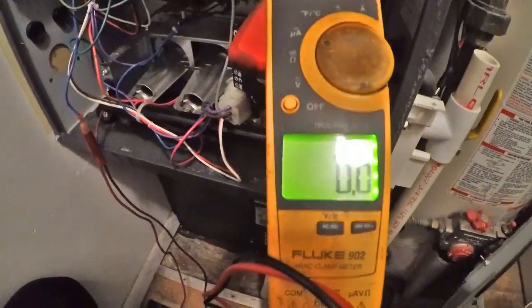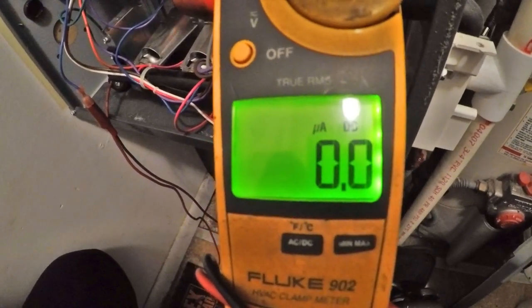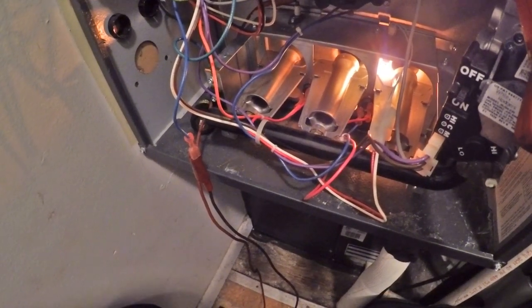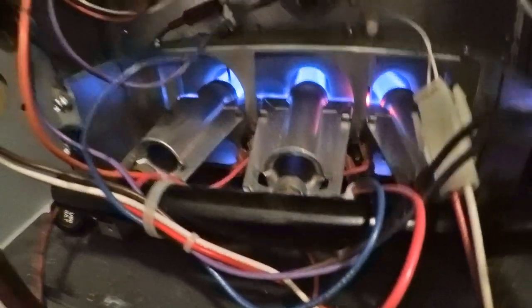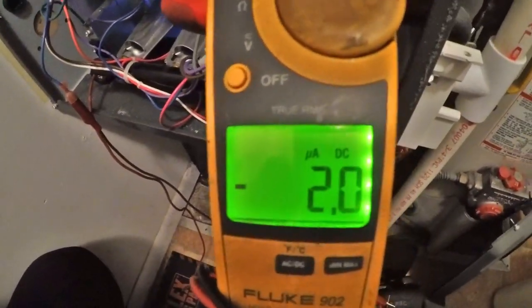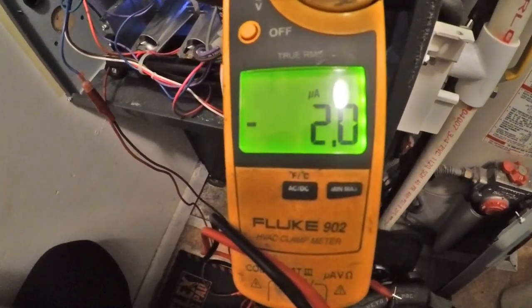We're going to read the microamps on the meter again since we cleaned it — first getting ready to light. There's our flame signal. A dirty flame sensor is going to cause your furnace not to come on and stay running.